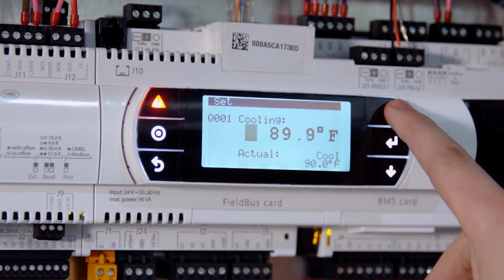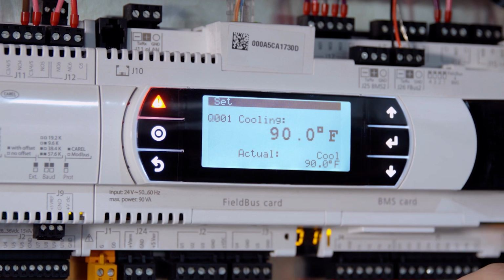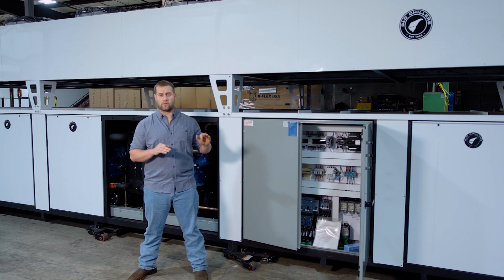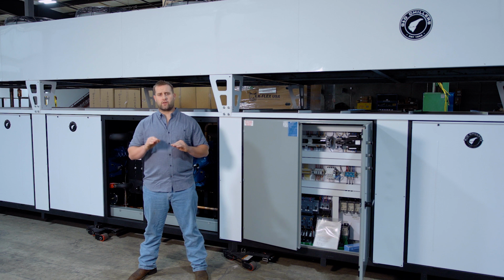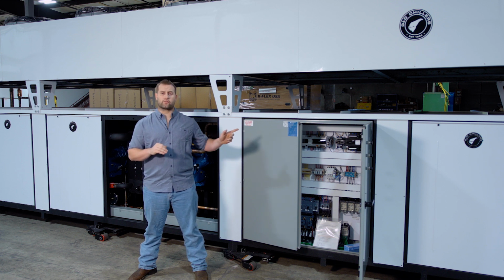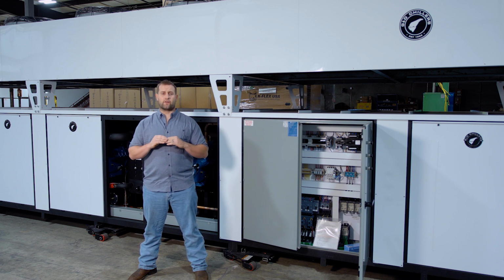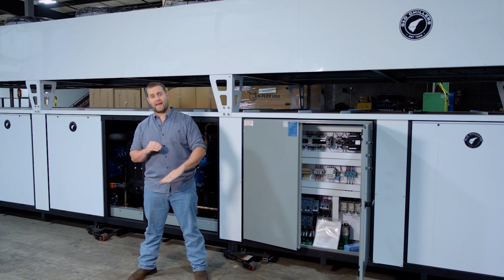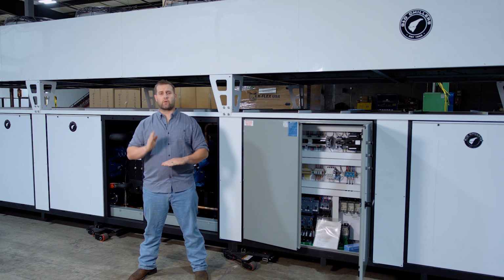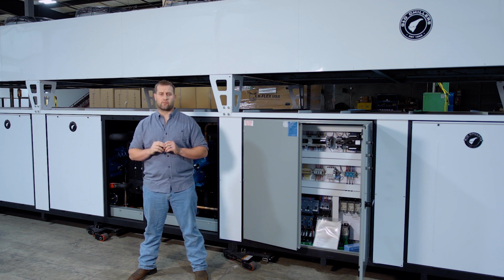It is important to note, for these scroll compressors, if you have scroll compressors or a scroll chiller, once you get to this point you're going to want to verify the compressor rotation. How you do that is, once you have the compressor started, go to the info screens in the Carel and verify that your suction pressure is going down and your discharge pressure is going up. If that's the case, you know those scroll compressors are rotating in the right way.